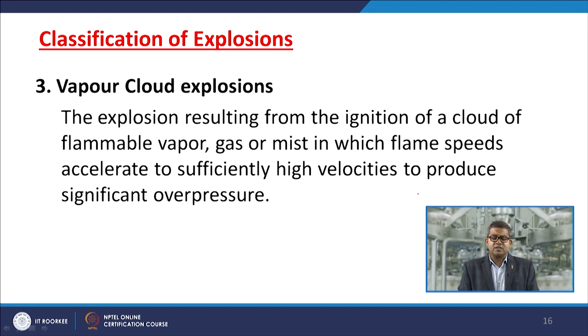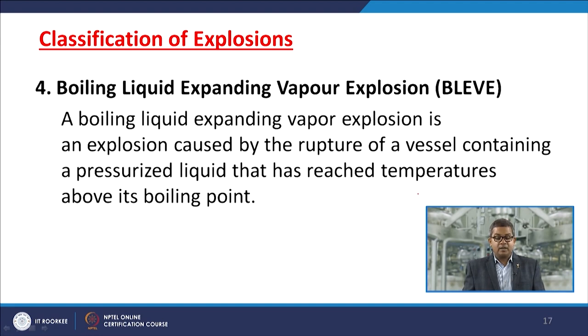The vapor cloud explosion is very common and extremely important. It is the explosion resulting from the ignition of a cloud of flammable vapor, gas or mist, in which flame speeds accelerate to sufficiently high velocity to produce significant overpressure. This is extremely dangerous. A lot of accidents in history are attributed to vapor cloud explosions.